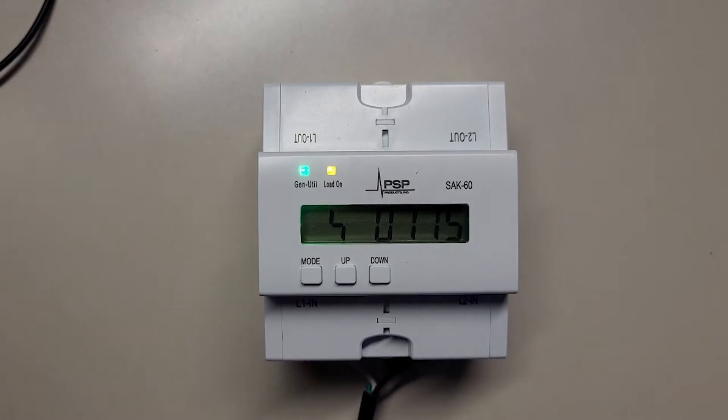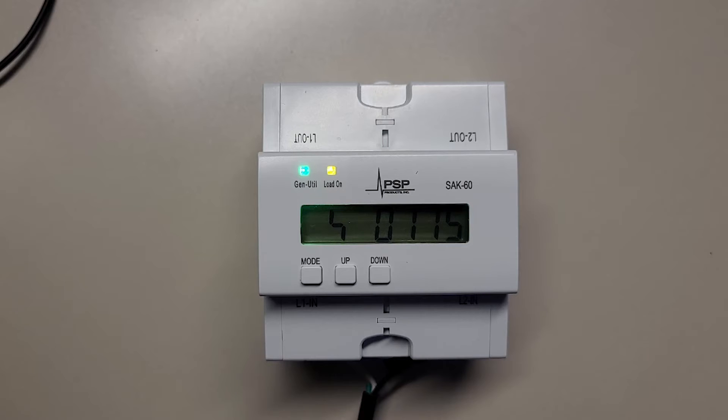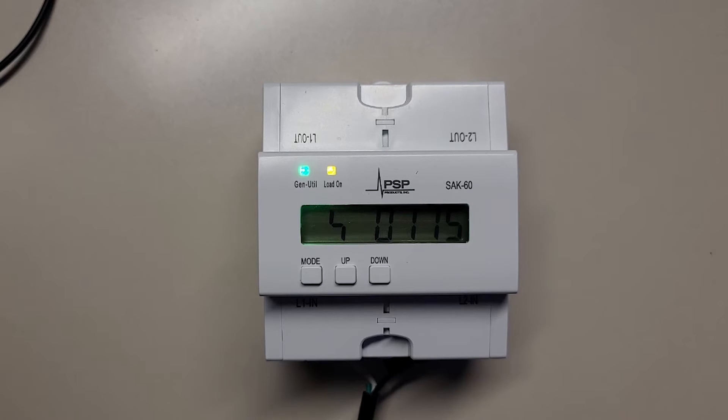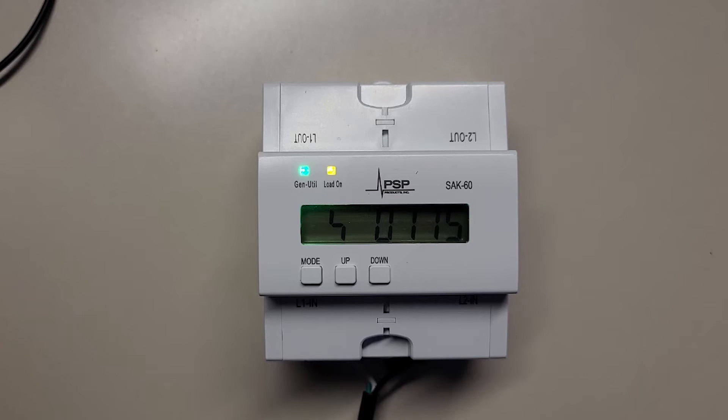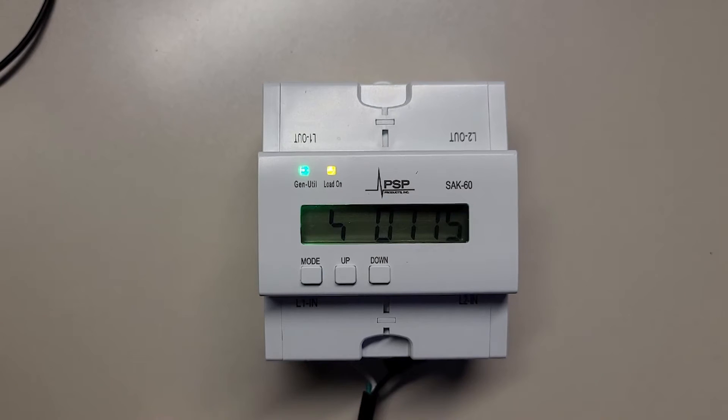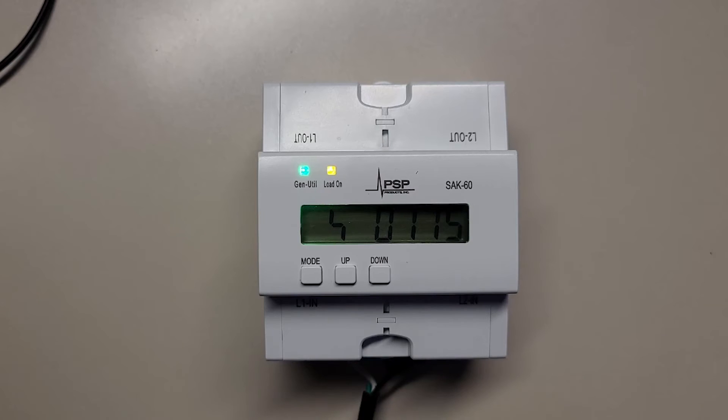Once you've started to program it, if you press no buttons for five seconds, it will save the changes you've made and reload the program with the new values. That whole process of saving and reloading takes about 30 seconds and the SAK will accept no inputs during that time. There's no point in mashing the mode button. It's just going to mess you up. Just settle down and be patient. Do not worry if you accidentally change a value and it saves, you can always go back and correct it.